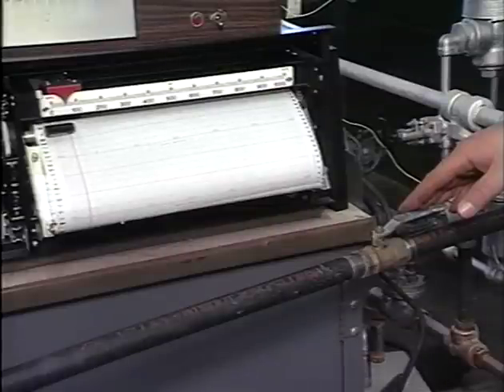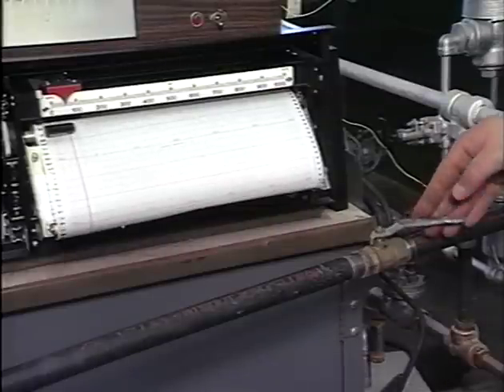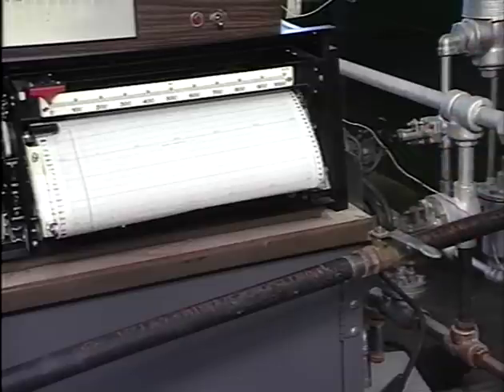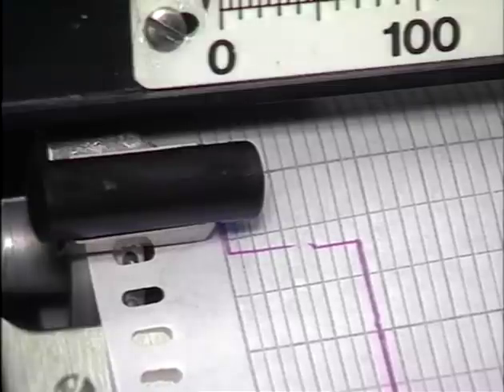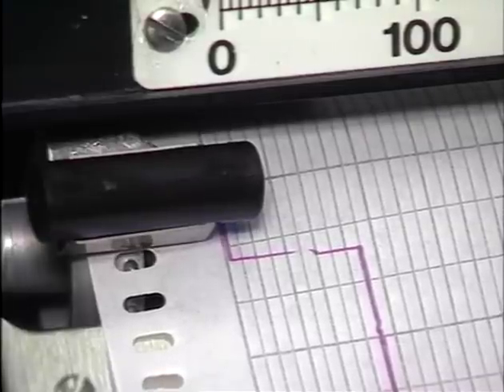By closing the valve slowly, the velocity of the water is reduced before the column is stopped. Since the momentum of the water is decreased gradually, damaging water hammer will not be produced.